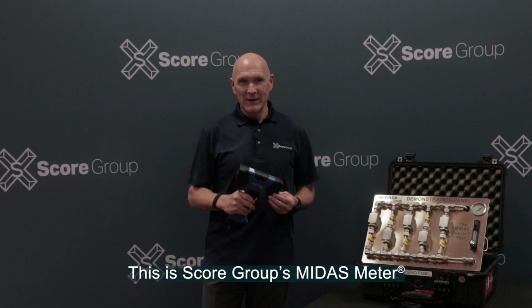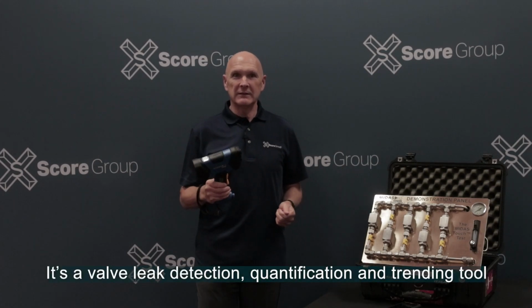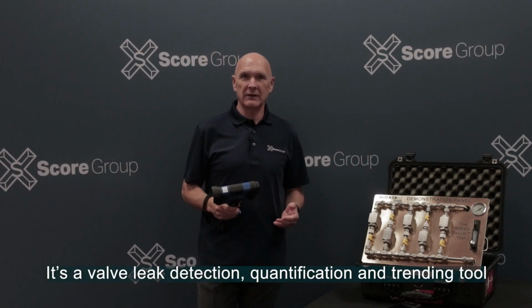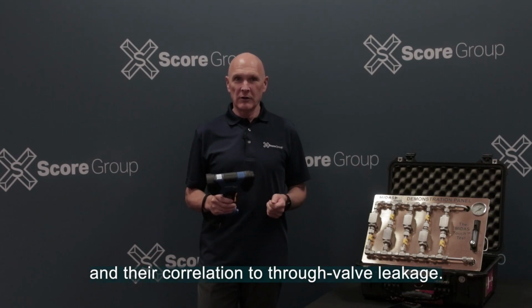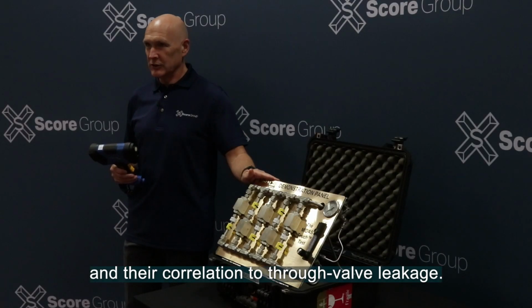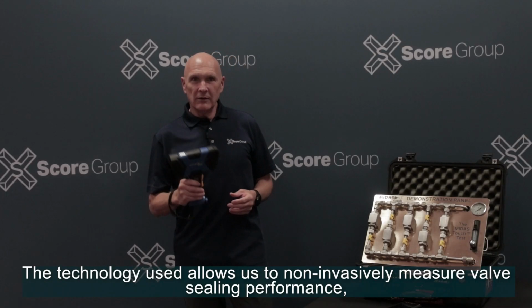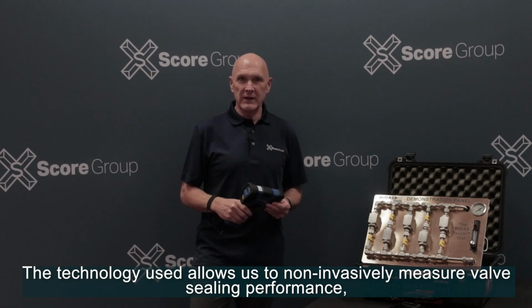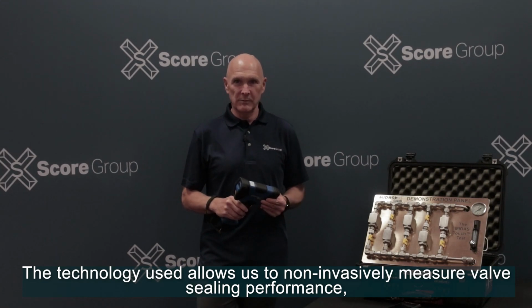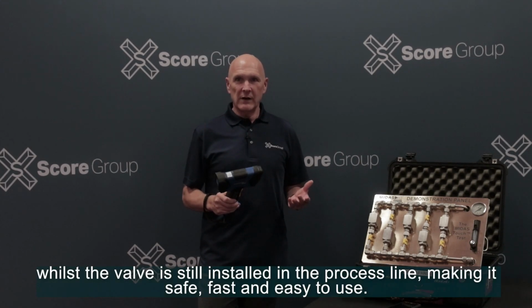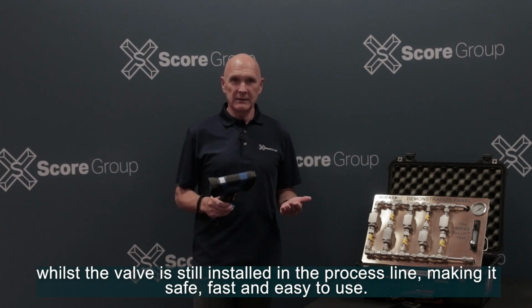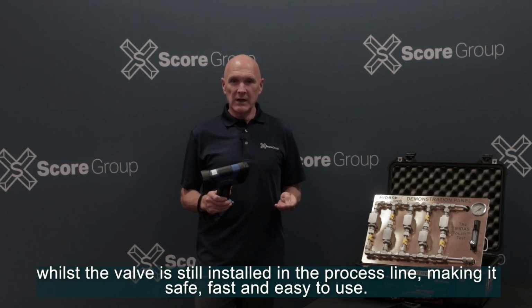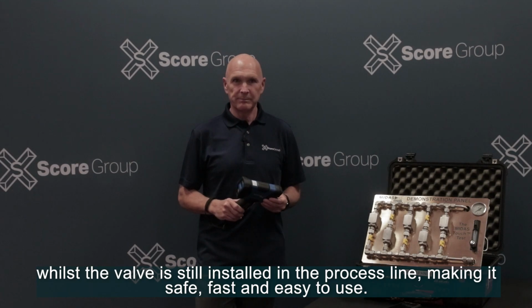This is Score Group's MIDAS meter. It's a valve leak detection, quantification and trending tool that's been developed over 40 years of research into acoustic emissions and their correlation to through valve leakage. The technology used allows us to non-invasively measure valve sealing performance, whilst the valve is still installed in the process line, making it safe, fast and easy to use.